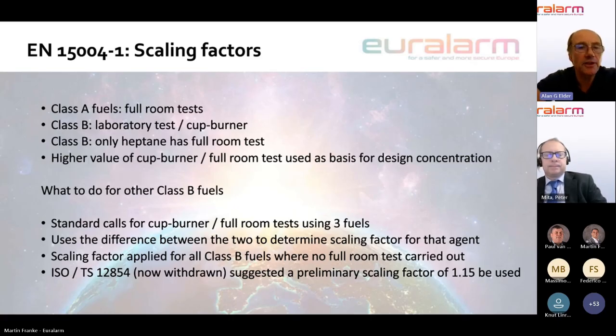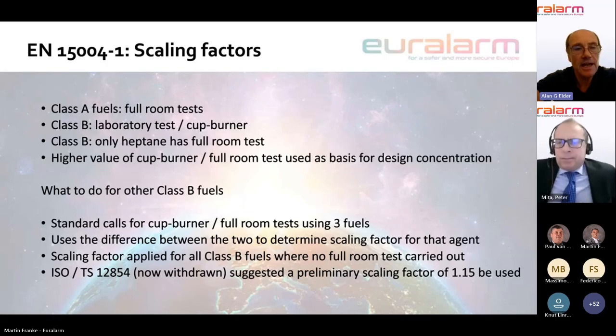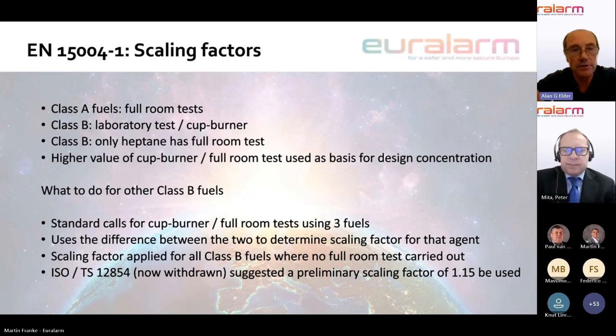In respect to Class B materials, which are flammable liquids, the requirement in the standard is to carry out a cup burner test, which is a small-scale laboratory examination of the extinguishing concentration of the material. Only heptane has a full room test. So where we have with Class A fuels a full room test, we're only required to do that for heptane. So with the heptane as the fuel, we take the higher value of the cup burner value and the full room test, and that is used as the design basis for the design concentration. And so the question is asked, well, what to do for other Class B fuels? Because other Class B fuels may behave differently in those two experimental examinations than heptane does. And we do know of some examples where a cup burner value is given for a Class B material, but the full room may actually result in a higher value.